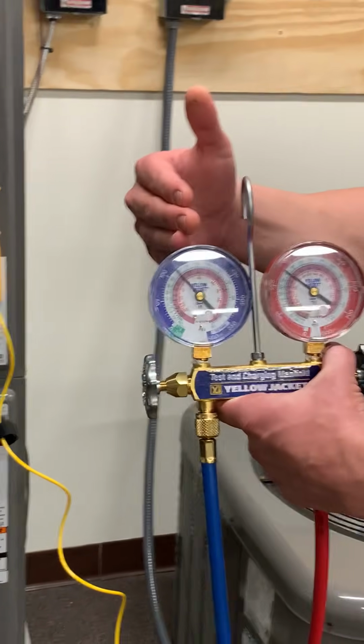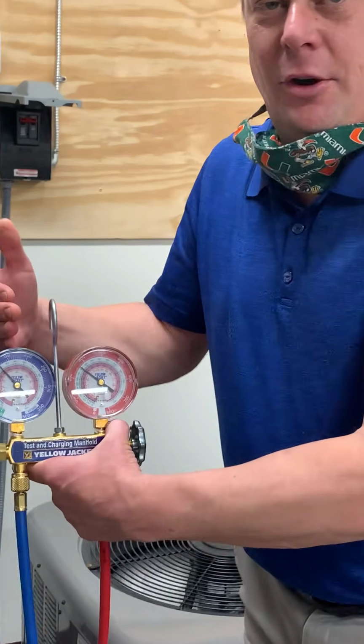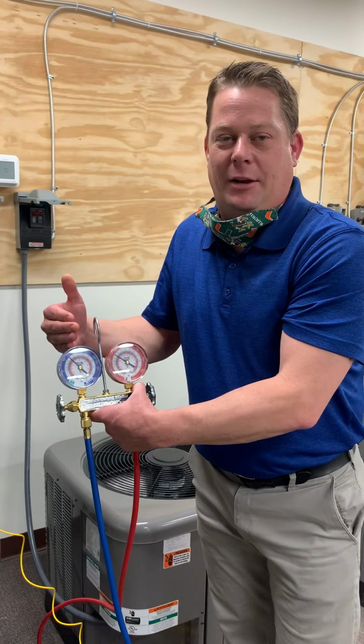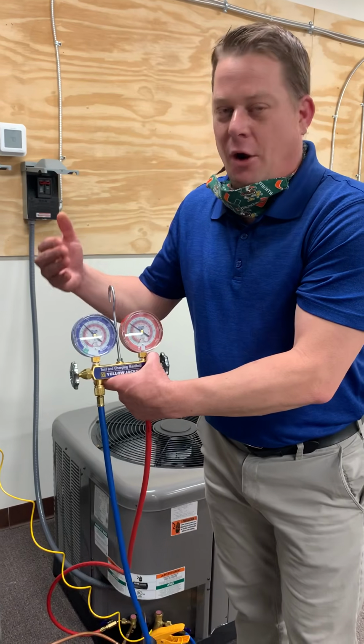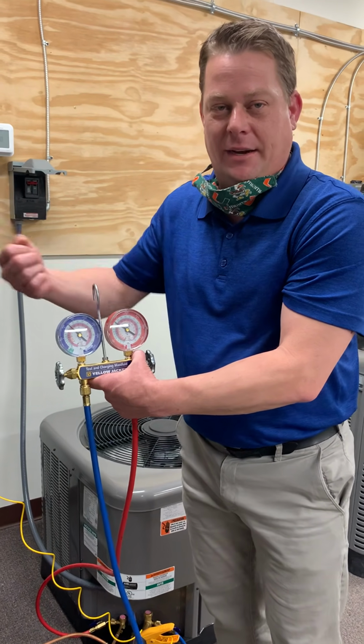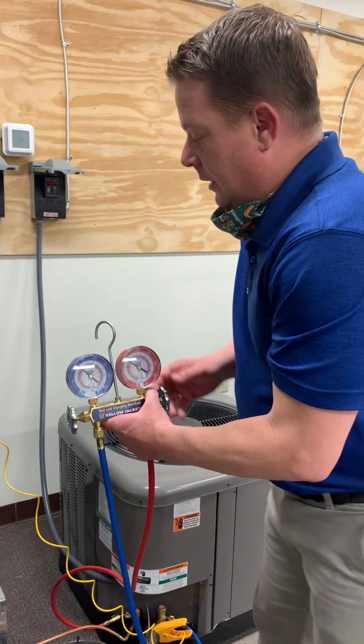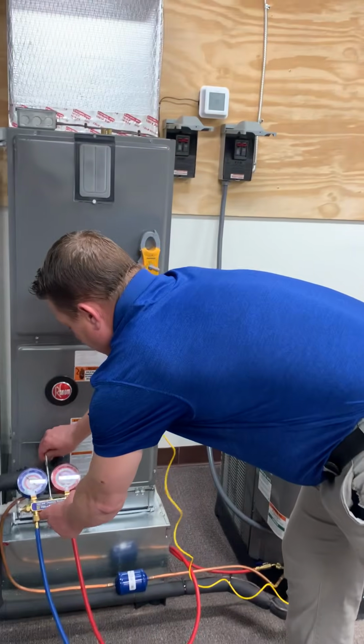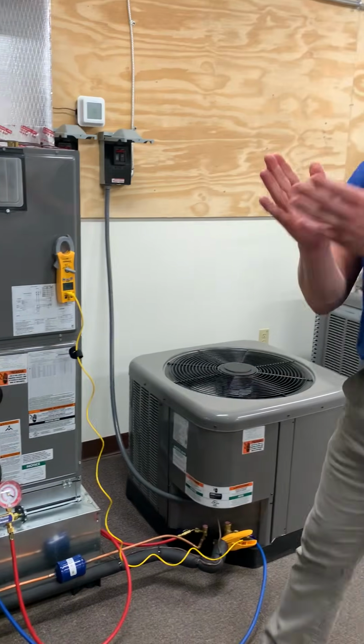Superheat means I have a vapor. Probably the worst thing for a compressor is having liquid flood back to it. So knowing I have superheat lets me know I have vapor coming back to the compressor, and I'm not going to slug it. The next reading I'm going to take is the subcooling reading.